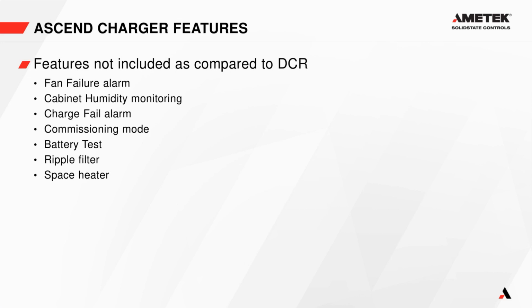Commissioning mode was used for commissioning, I believe it was NiCad batteries. They have to be commissioned at a higher voltage than lead acid. We don't offer the battery test function. We don't have an AC input or an output ripple filter because we don't need it, and we don't have a space heater available either.